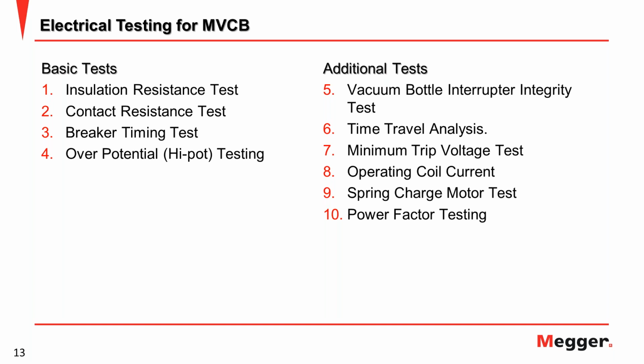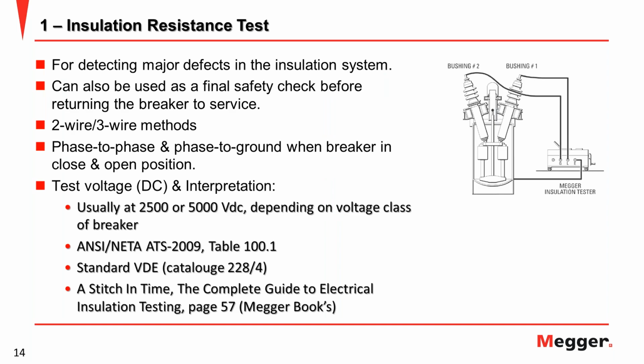Now I will try to explain the tests one by one, so you can define later which one is very important for your system. Okay, the first test is the insulation resistance test. This test is actually not mentioned in any standard regarding circuit breaker tests, but if you see insulation resistance testing in general, normally we need to test the insulation resistance of all electrical components first before you continue to other tests.